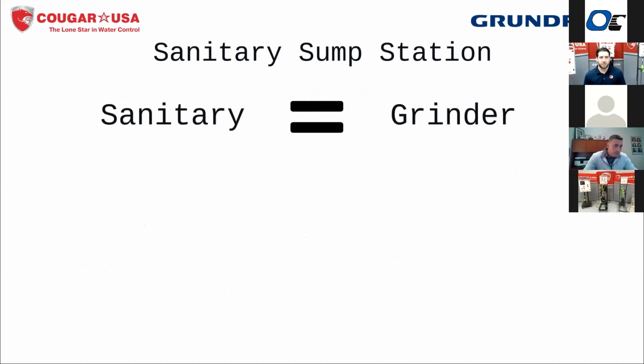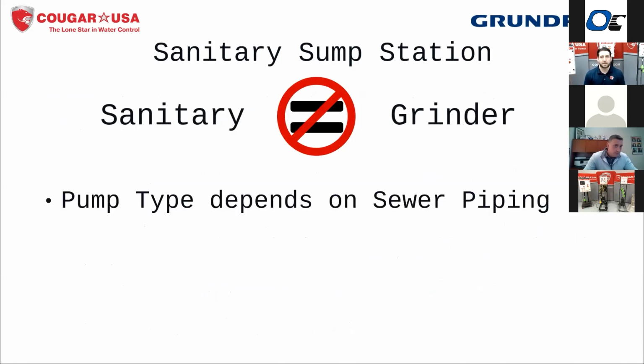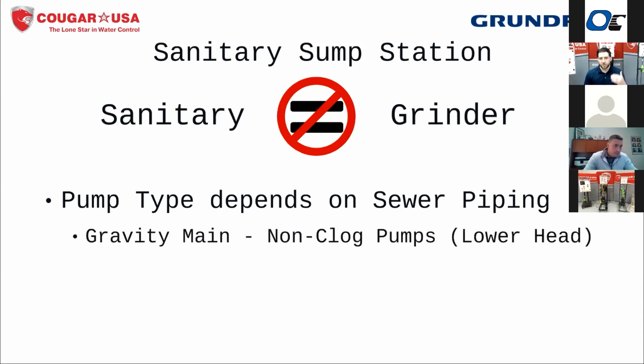So a lot of times here we'll get questions, and a lot of times this comes from the plumbers in the field where they're saying, hey, I got a sanitary pump that went bad. I need a new pump. I need a grinder. There's this assumption that because it's a sanitary pit you have to use a grinder, and that's not really the case. You're going to want to select the pump based on what you are pumping into as well as what you are actually pumping. So we don't want to choose a grinder just because we have a sanitary pit and we have solids. We can use non-clog style pumps to move sanitary waste if we are pumping into a gravity main. Okay? We have much less head requirement to get from the pit into the gravity main.